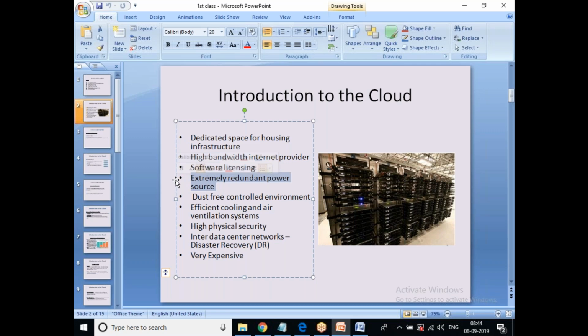So you need a proper UPS system. If the UPS system is also running out of power, you need proper generators to supply power to the servers so that you don't see any outage. So you need to design it in such a way that you have all the alternatives.